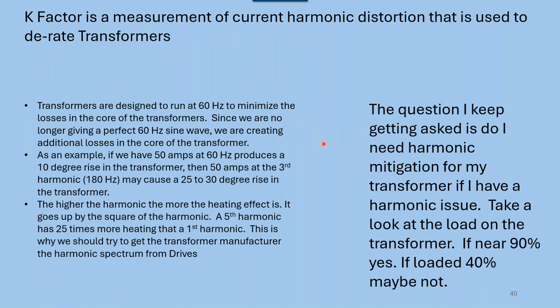So this is what this is all about. Transformers are designed to run at 60 hertz, and that's all great and wonderful. But if I've got 50 amps at 60 hertz, I may get a 10-degree C rise in the transformer. That same 50 amps, if I'm running it at a third harmonic, can cause anywhere from 25 to 30 degrees additional rise in the transformer. Why is that? Because the higher the frequency, the more skin effect it has, so the current wants to travel closer to the surface of the conductor. Here you can see a fifth harmonic is generating 25 times more heat than a first harmonic.